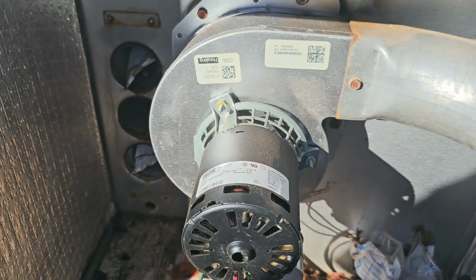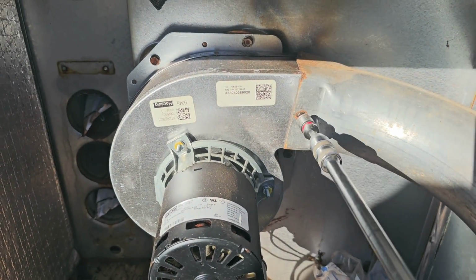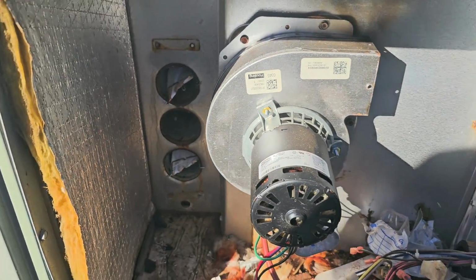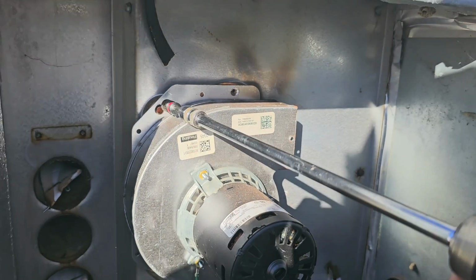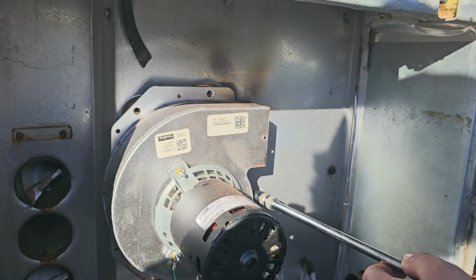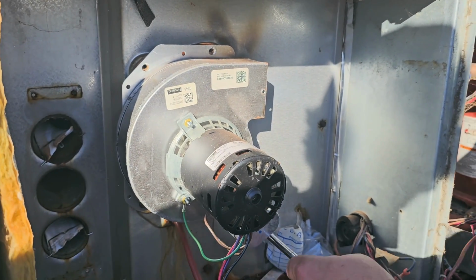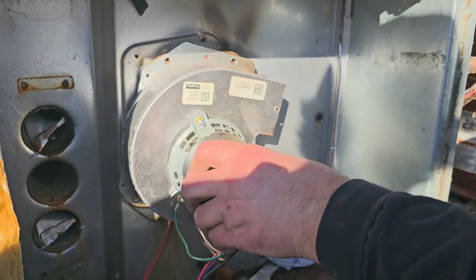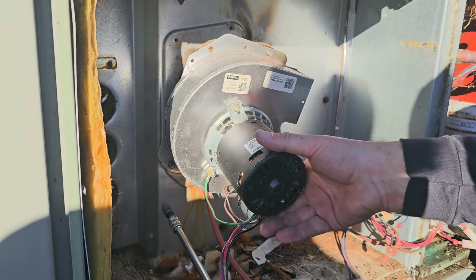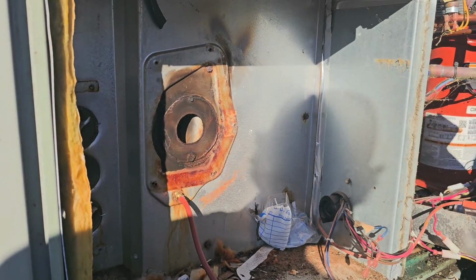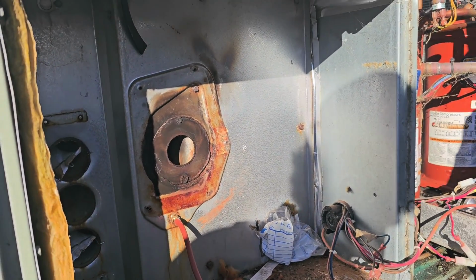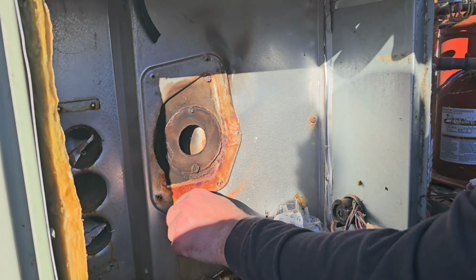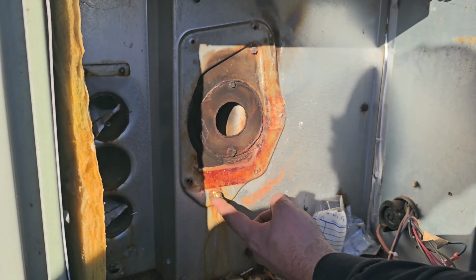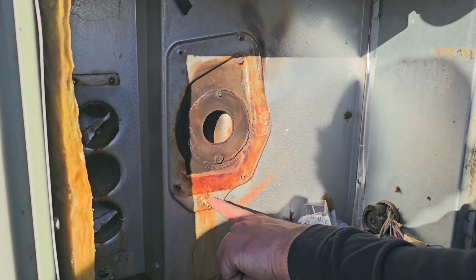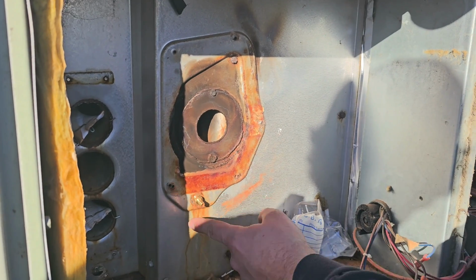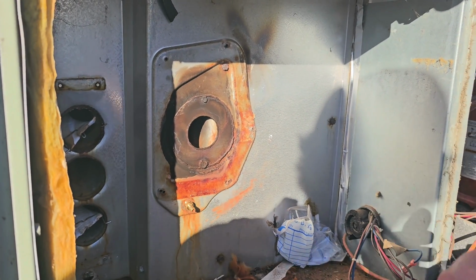Now I want to take off the inducer motor, as well as the little flue pipe here. All right, now inducer motor. I just replaced this. And also, when I replaced this motor, you can see that I had to put in a new fitting for the pressure switch tube. I go to the supply house, I get a brass barb fitting. One side is threaded, one side's barb, and that's how I make that fix.